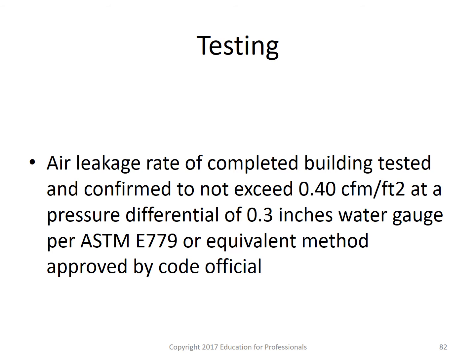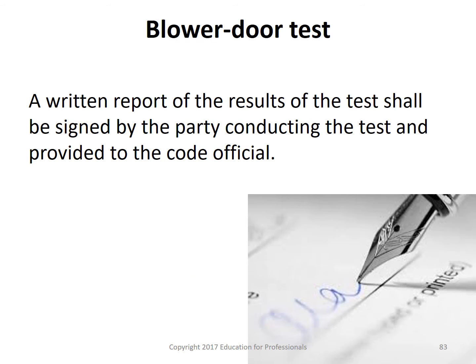And moving to the testing of air barrier integrity, which is the testing through an air leakage rate. The air leakage rate should be confirmed not to exceed 0.40 cubic feet per minute per square foot at a pressure differential of 0.3 inches water gauge, per ASTM E779 or an equivalent method approved by the code official. And finally, a written report of the results shall be signed by the party conducting the test and provided to the code official.